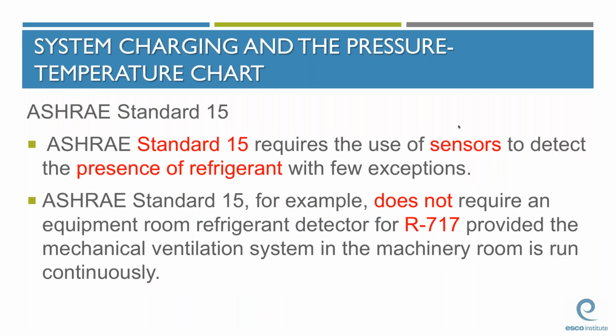On the refrigerant safety front, your students definitely need to know about ASHRAE Standard 15. This standard requires that a refrigerant sensor be located in equipment rooms. These sensors will trigger an alarm and automatically start a ventilation system if unsafe concentrations of refrigerant are detected. It's also important to note that some applications, such as equipment rooms that use R717 ammonia, don't require a leak sensor if the room's mechanical ventilation system is continuously operated. And that pretty much sums up type 2.